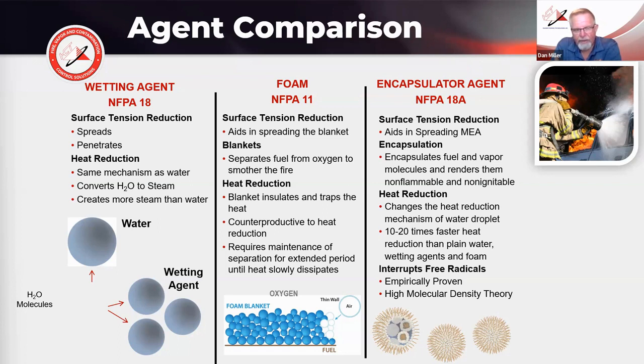NFPA 11 compatible foams have surface tension reduction that aids in spreading the blanket around fixed objects and sealing on the other side, which is actually a nice benefit. That blanket separates the fuel from the oxygen to smother the fire and keep the vapors from mixing with oxygen in the vapor space. And then heat reduction: the blanket insulates and traps the heat in, which is kind of a negative of foam. It eventually cools, but it's a slow process compared to an encapsulator agent.